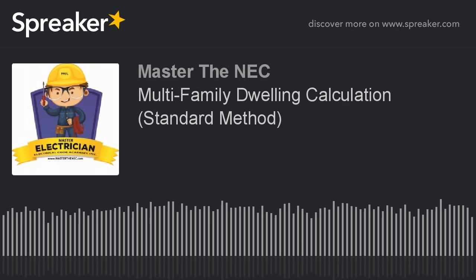Each one of these units also has a water heater that has 1.5 kW, or 1.5 kilowatts, and it's a 240 volt appliance, and it is a fixed appliance, obviously. The next thing we have is a 3 horsepower air conditioner at 240 volts. And of course, since it says 3 horsepower, you're going to have to find out what the actual amperage is of that by going to 430.248, because it is a single phase.